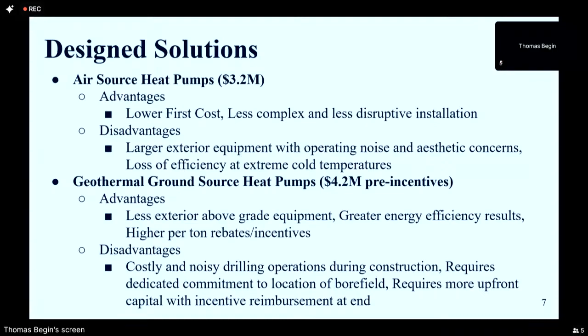As mentioned, the advantages of an air source heat pump are a lower first cost and a less complex and less disruptive installation. However, the disadvantages are larger exterior equipment with some noise and aesthetic concerns to address, and also loss of efficiency at extreme cold temperatures. Alternatively, another all-electric replacement for these gas boilers and heating systems is a geothermal ground source heat pump. The advantages there are less exterior above-grade equipment, greater energy efficiency results, and higher rebate incentives. However, the disadvantages are a costly and noisy drilling operation during construction. It requires dedicated commitment to the location of a bore field somewhere on site, and requires more upfront capital with incentives and reimbursements coming at the end.